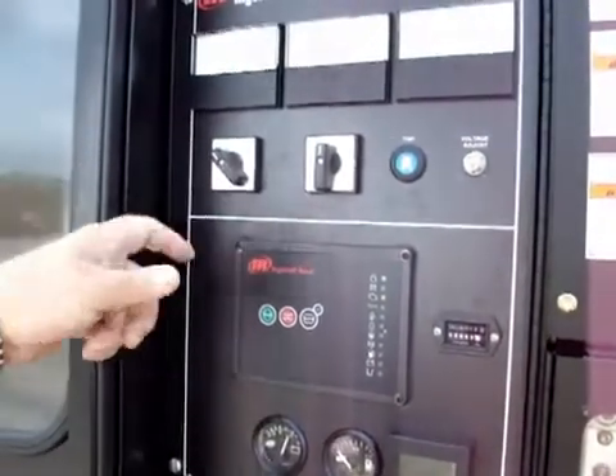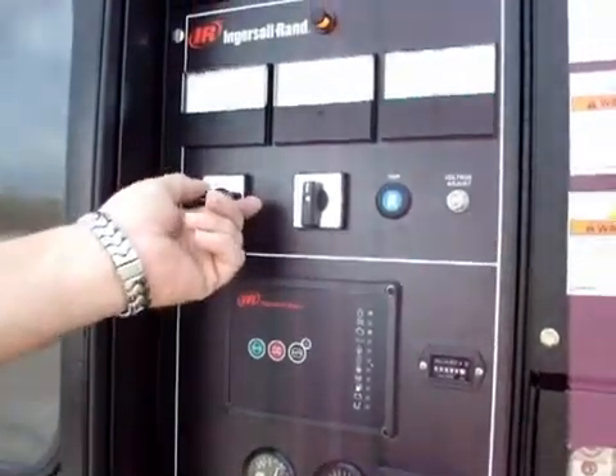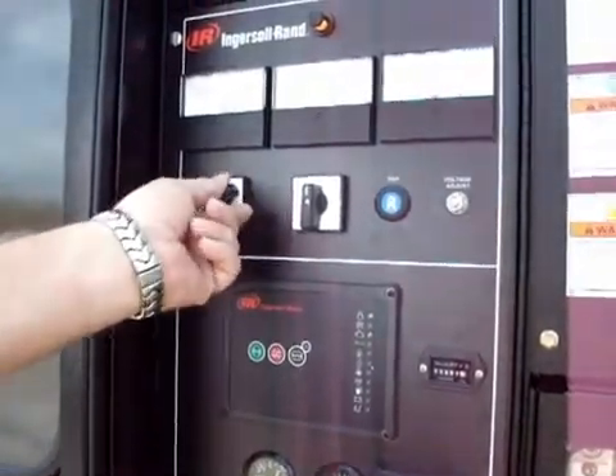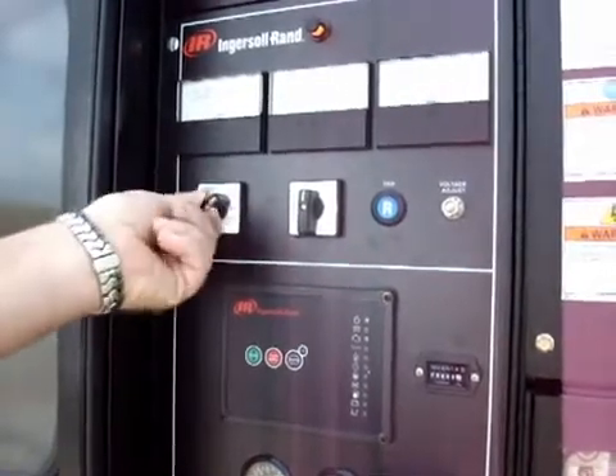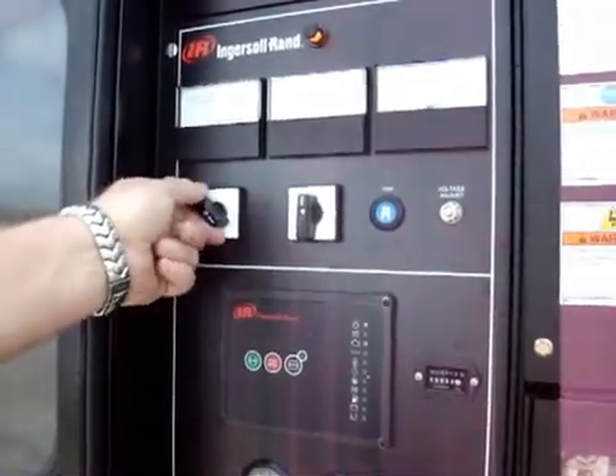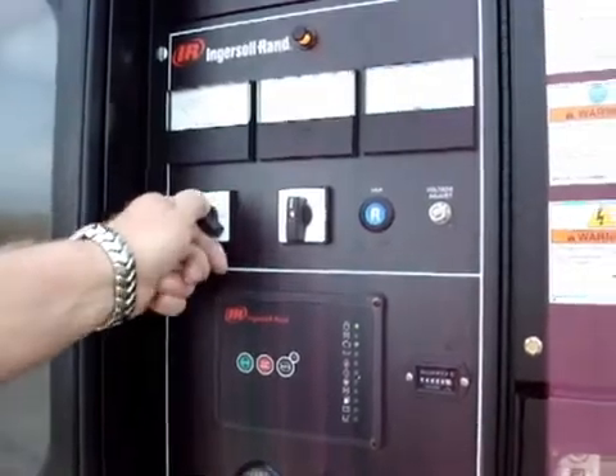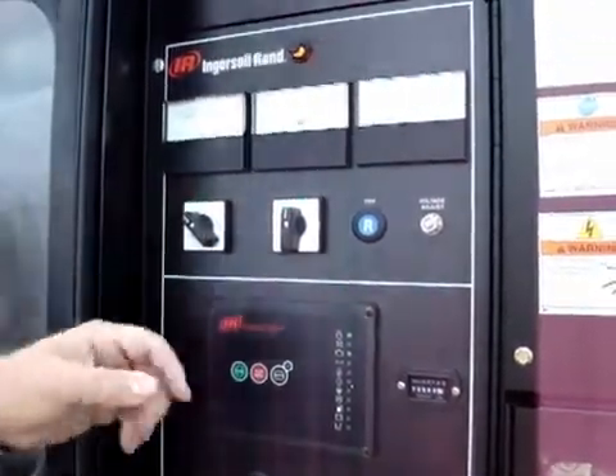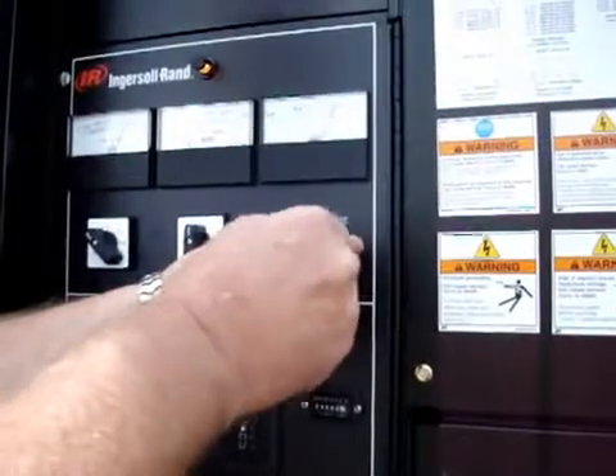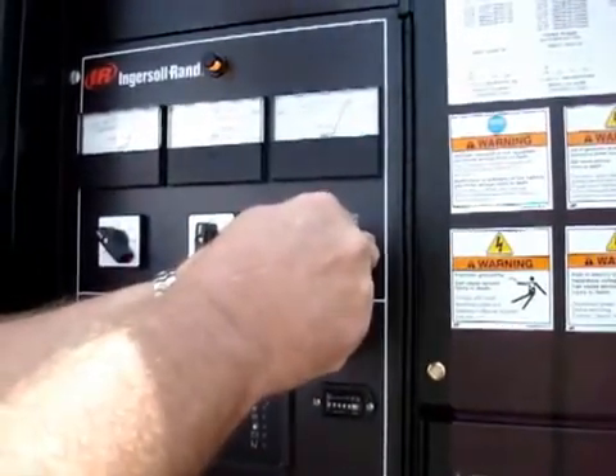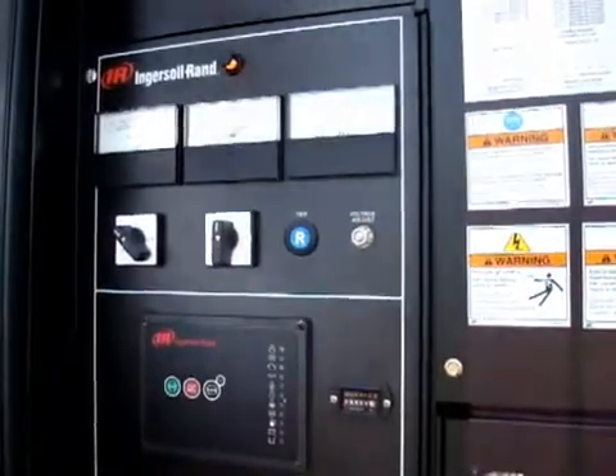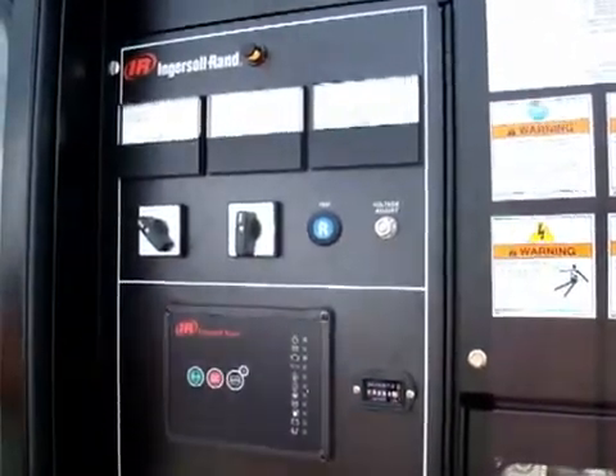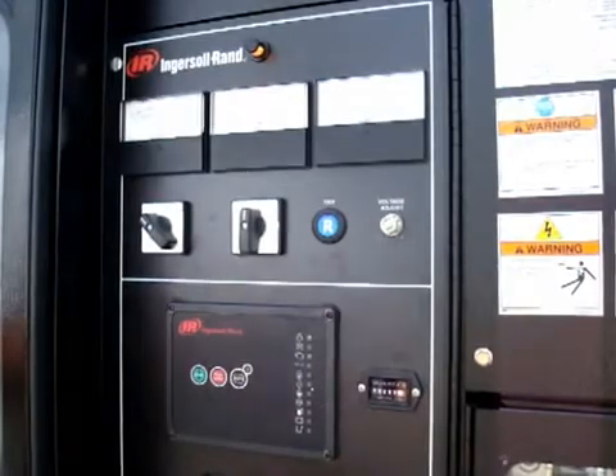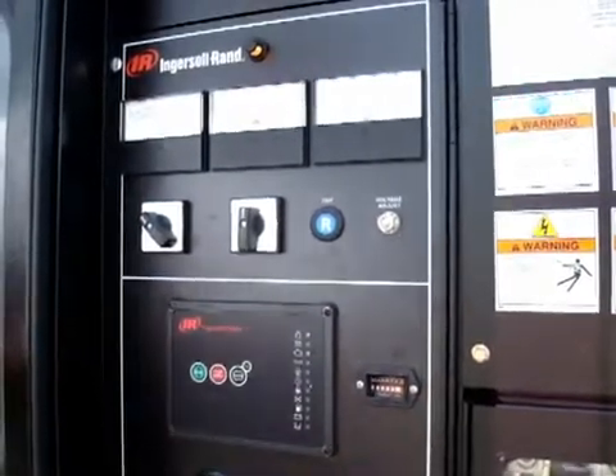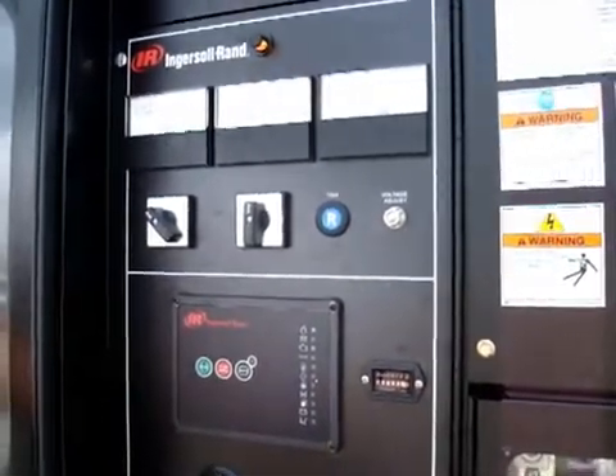Going with the voltage selector switch, we can check the voltage output, all three legs. And if we needed to make any adjustments, just adjust the pot accordingly, set the output voltage where we want. At this point, we will let the machine warm up for 3 to 5 minutes before shutting the output breaker and placing any load on the generator.